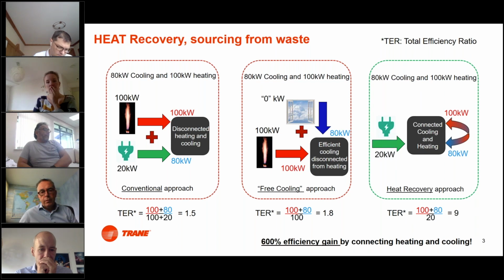And now with the electrification of heating, we start to have more discussions to combine the two elements of heating and cooling within the same process. By doing that, we are diminishing the use of fossil fuel combustion and connecting the dots of heating and cooling. In fact, we use everything that the cooling process is rejecting as a heating source to reduce the consumption of that fossil fuel. And in this example, depending on the temperatures, the efficiency can go up.